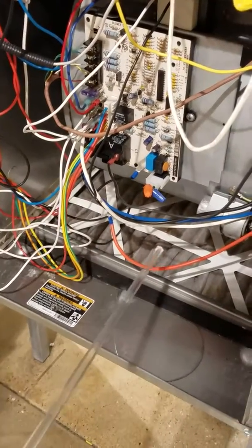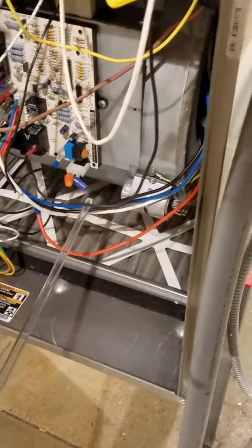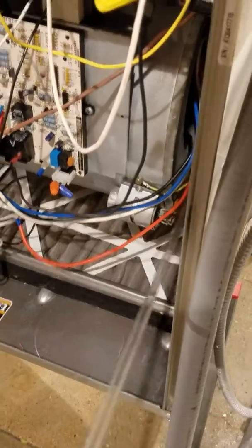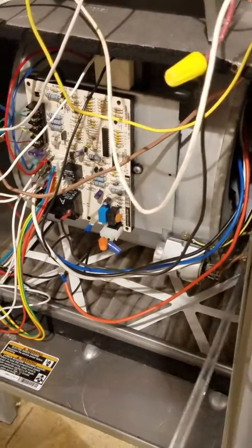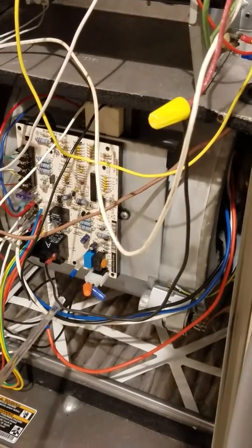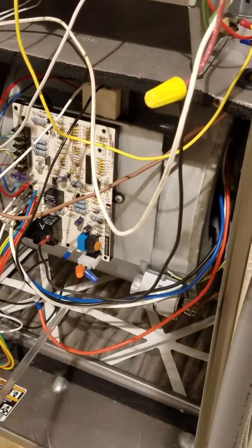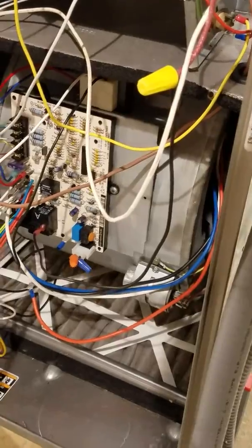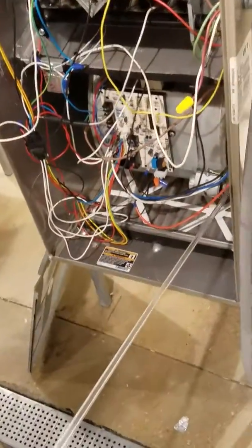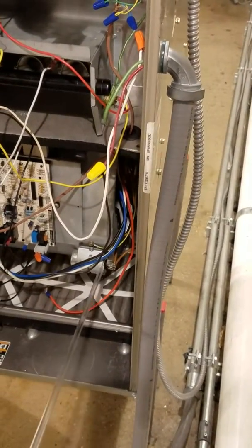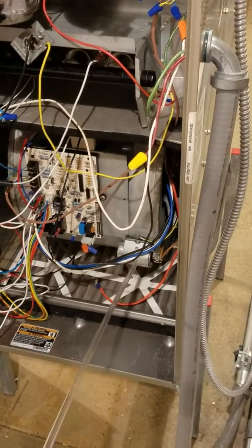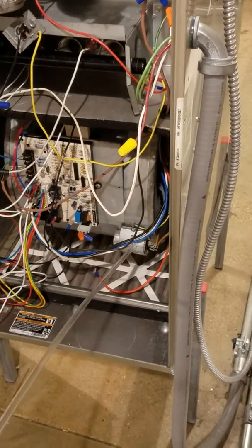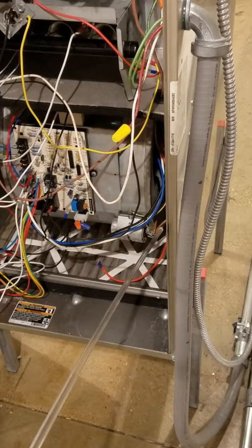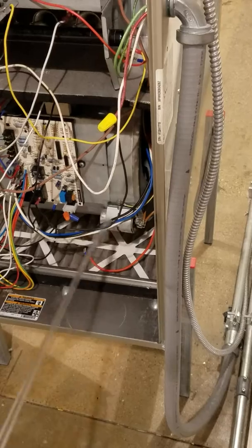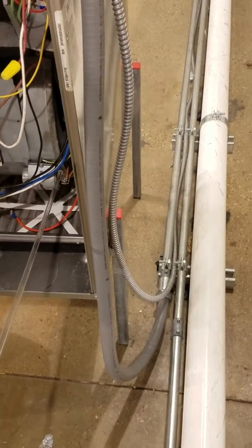All right. So now, since it's only a 2-speed motor, I need to hook up only 2 wires, but it has 4 wires. So out of 4, no, actually it looks like a 5. Okay, so out of 5, black on cool, orange on heat, medium speed, high speed, and there'll be 1 more wire which is blue that I will put on park because I don't need it. So I will put it on park, and then the other 2 wires which are brown, they will go on my capacitor, single capacitor, not dual capacitor, but single run capacitor, by the way. And that's right here. So those 2 browns will go here. Okay. Sometimes it has only 1 brown. In that case, you put 1 brown there, and you bring a power wire that will go to the other terminal because it needs power.